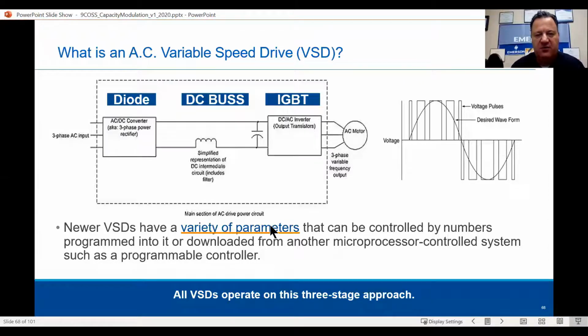Newer VSDs have a variety of parameters that can be controlled by numbers programmed into it or downloaded from another microprocessor controlled system, such as a programmable controller. Now, all VSDs operate on this three-stage approach. Again, diodes, AC to DC, converted over, aka three-phase power rectified. Then we've got the DC bus. Again, think of this as a capacitor if you're not familiar with it, okay?